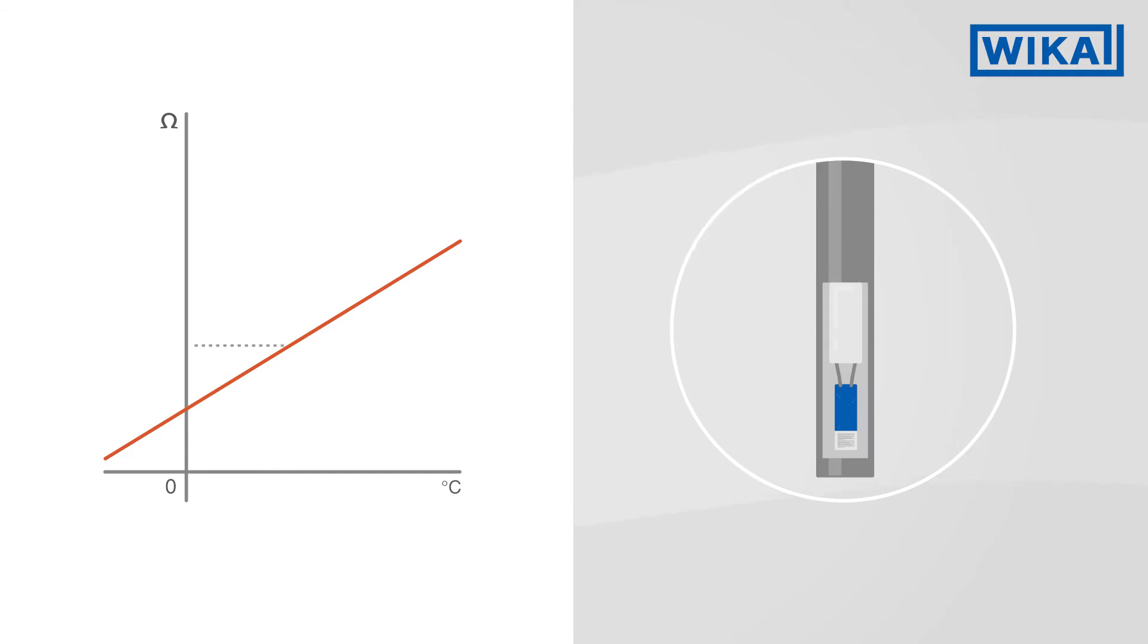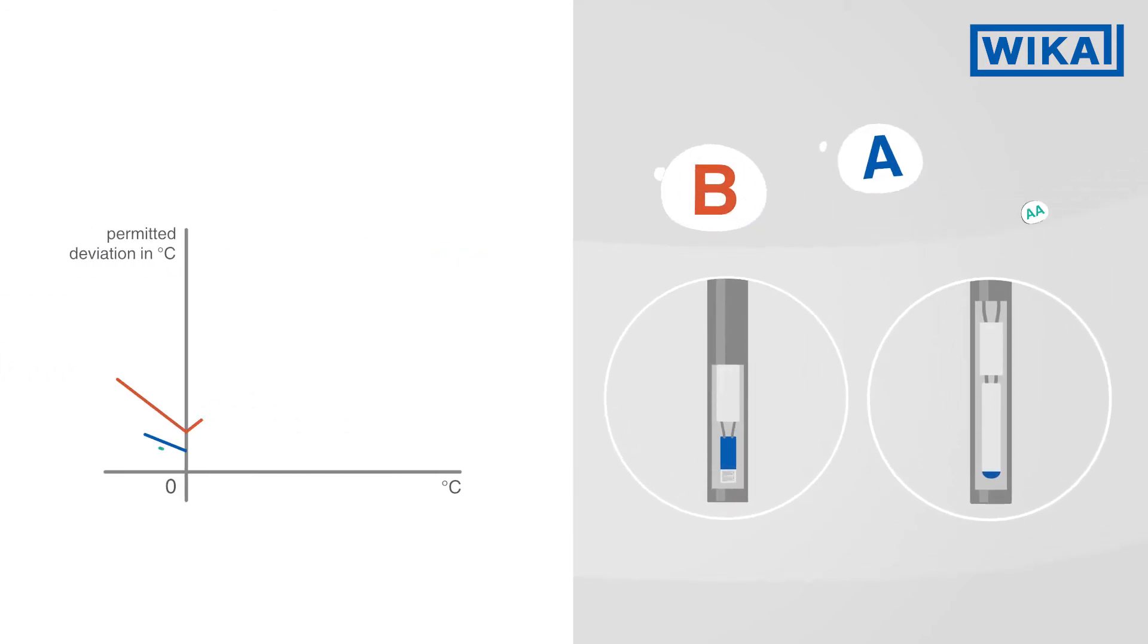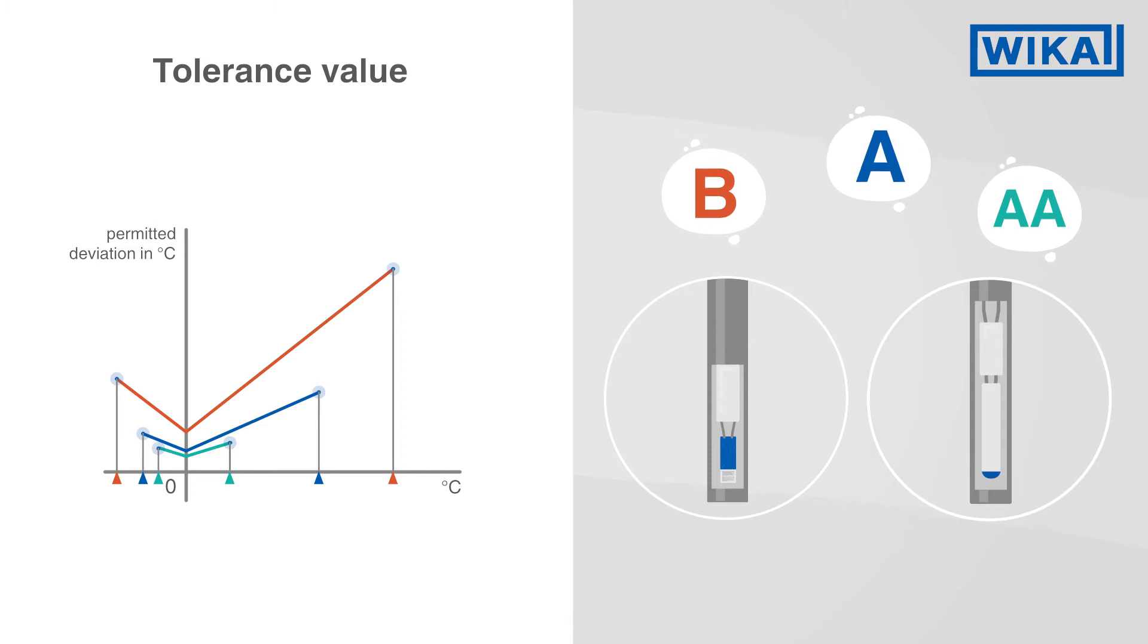By measuring the resistance, the temperature can be determined very accurately. Resistance thermometers are available in different accuracy classes. For standard versions with increasing accuracy, the measuring range in which they can be used shrinks.